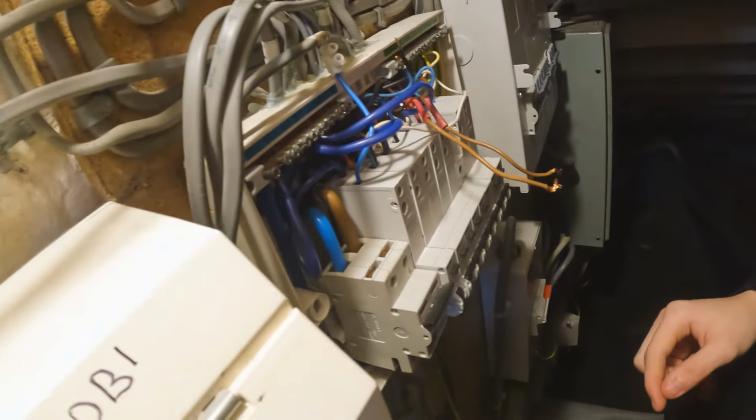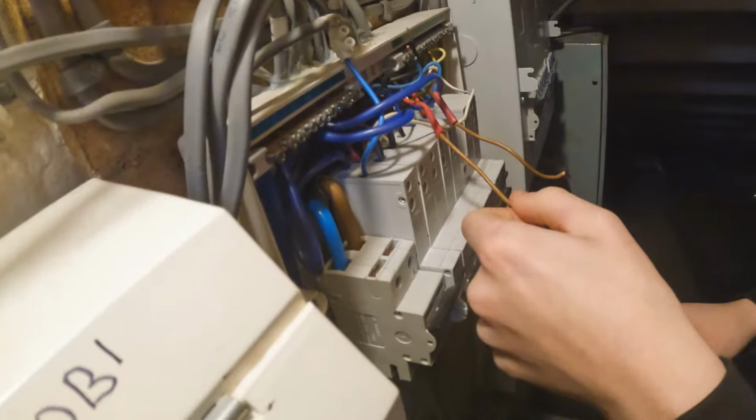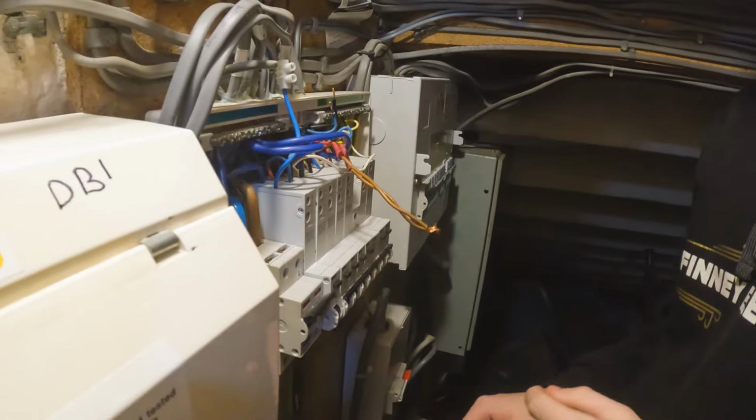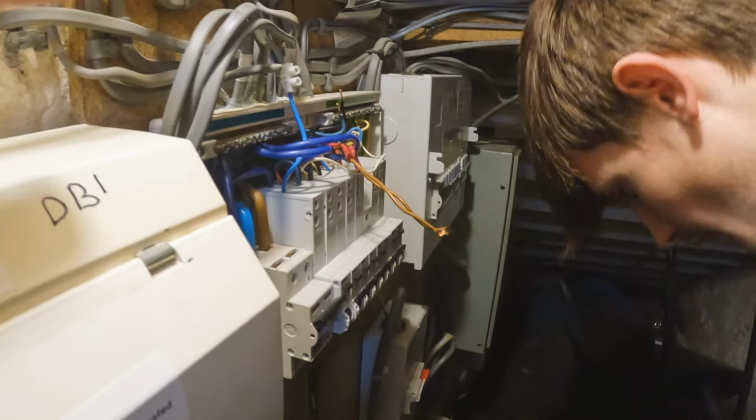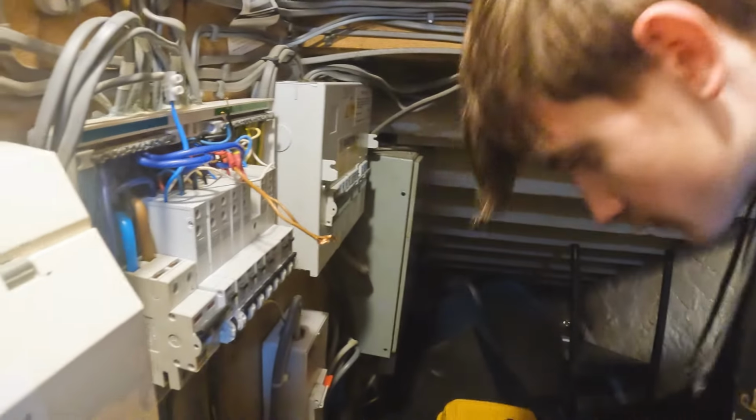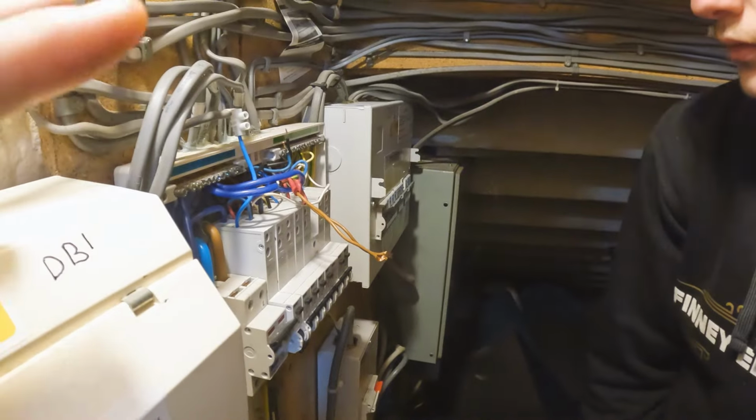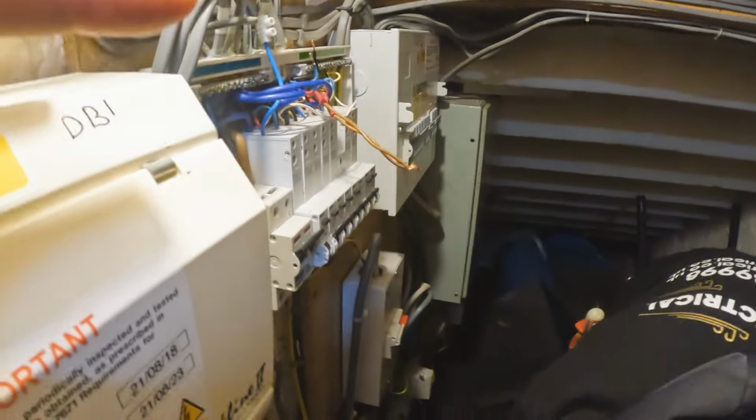I bet the new colours will be the emergency lighting, because they said the emergency lighting went off, and the old colours will be the lighting in there and that little storeroom. So should we get the tester out and test? We could test the RCD as well, which might be wise to make sure that's working and there's nothing wrong with the circuits, but we need to test both, don't we?